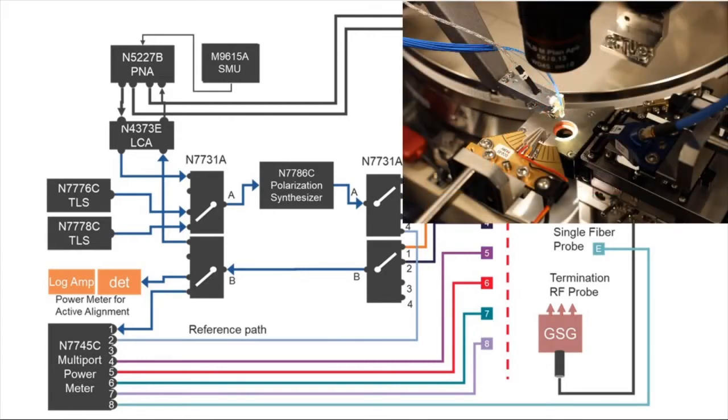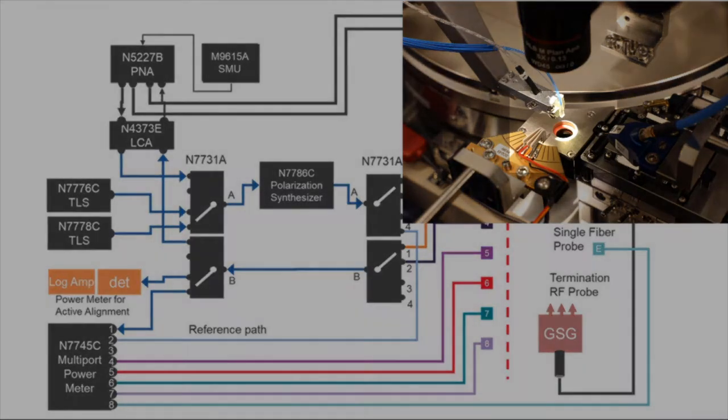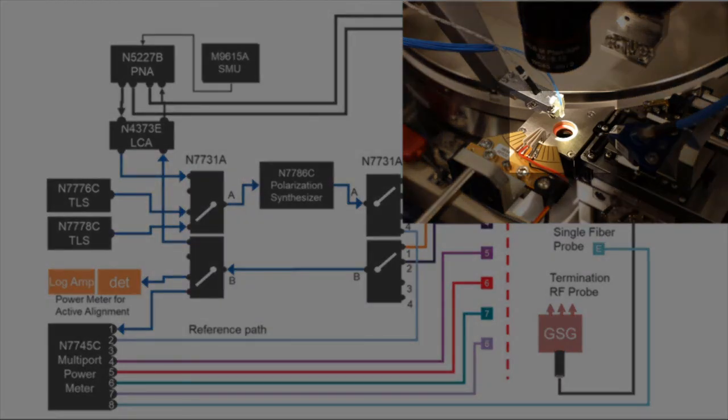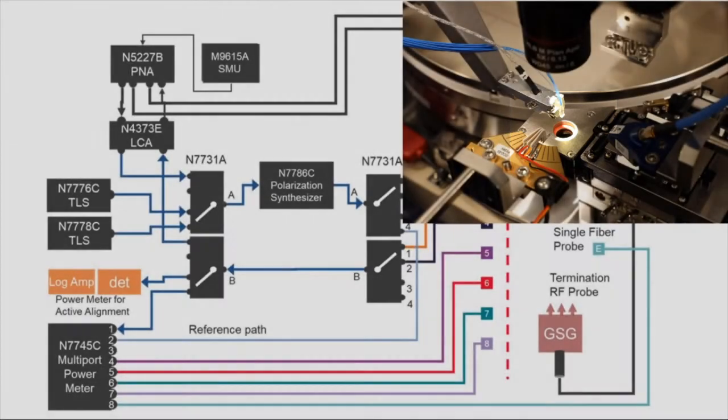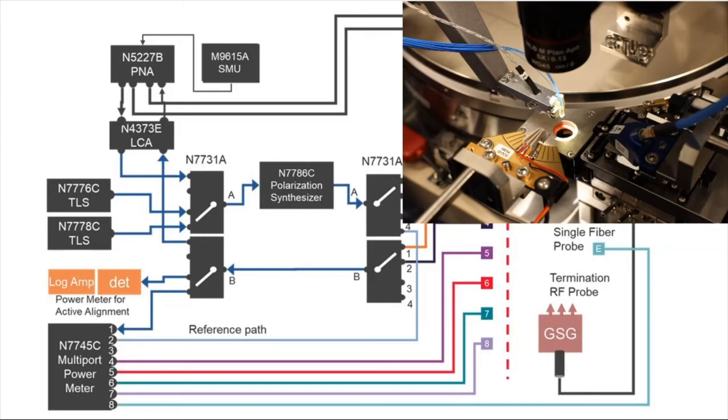With a very sophisticated calibration concept using the built-in photo detector or power meter in the probe station, we are able to de-embed and remove all the insertion losses of the fiber infrastructure to the DUT interface.